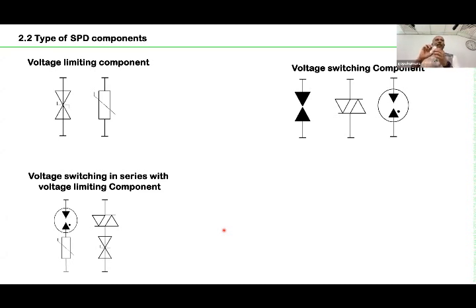So this is an SPD. Inside this casing, it is not only an MOV, it contains a thermal isolator. It is a pressurized silver soldering. Once the temperature is more than 80 degrees, it opens. Why that particular safety measure? Because MOVs will generate heat and die. A temperature of more than 80 degrees means it is going to die. So before it creates a short circuit, the thermal isolator will disconnect the MOV.